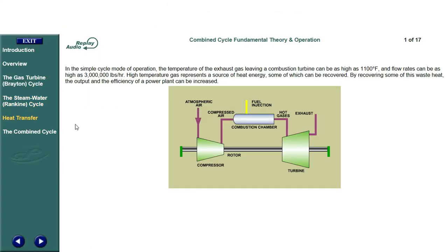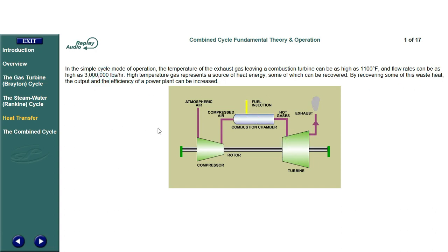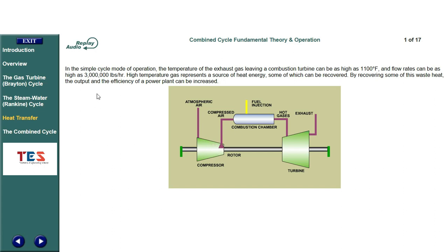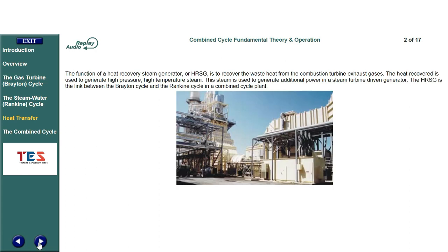In the simple cycle mode of operation, the temperature of the exhaust gas leaving a combustion turbine can be as high as 1,100 degrees Fahrenheit, and flow rates can be as high as 3 million pounds per hour. High temperature gas represents a source of heat energy, some of which can be recovered. By recovering some of this waste heat, the output and the efficiency of a power plant can be increased. The function of a heat recovery steam generator, or HRSG, is to recover the waste heat from the combustion turbine exhaust gases.